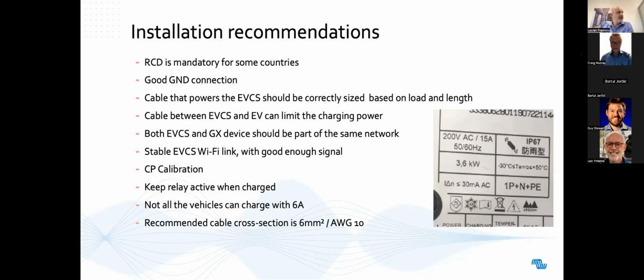Third point: make sure the cables powering the charging station are correctly sized based on load and length. If your vehicle charges at only 11 kilowatts, you shouldn't use too large a cross section. My recommendation is 6 square millimeters. Make sure you choose the right cable before using the charging station, to prevent risks of fire and other issues.